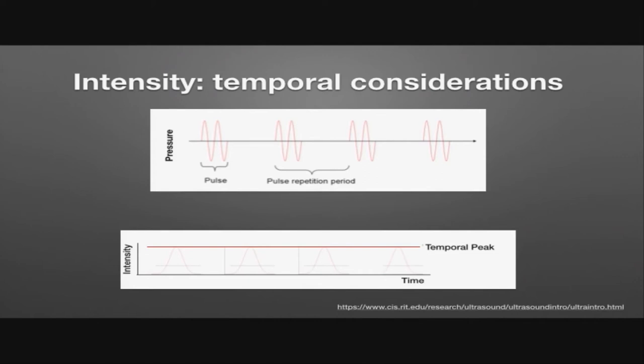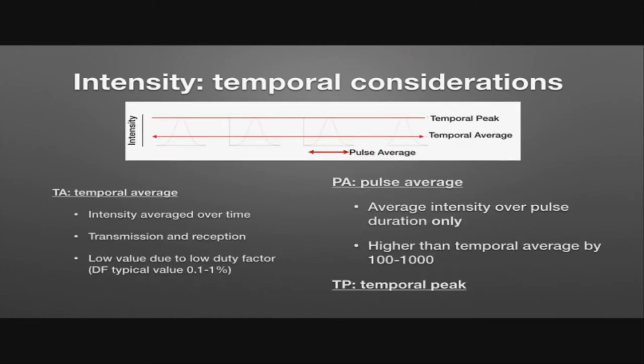The temporal peak value will be much higher than the temporal average, based on the duty factor — about 0.1% to 1% for B-mode and higher for pulse-wave Doppler. The temporal average is intensity averaged over time, including both transmission and reception, giving low values due to the low duty factor. The pulse average is the average intensity over that pulse duration only, which will be 100 to 1,000 times higher than the temporal average. The temporal peak is the single highest value reached within the pulse — not an average over reception and transmission, just that peak value.